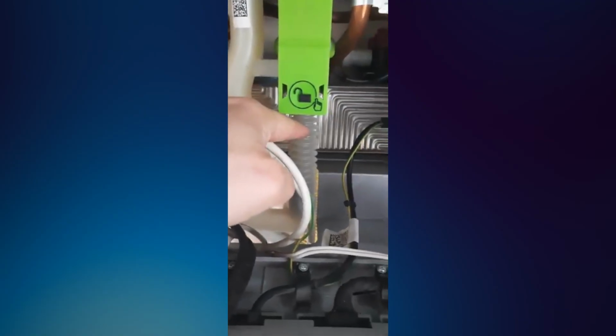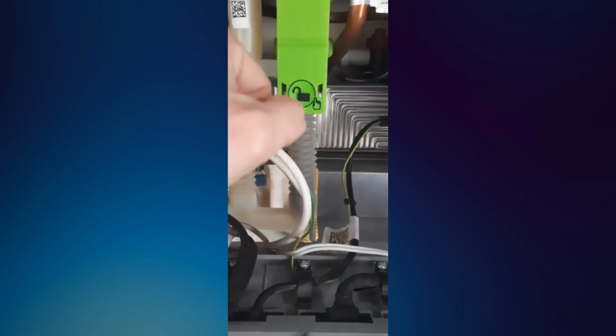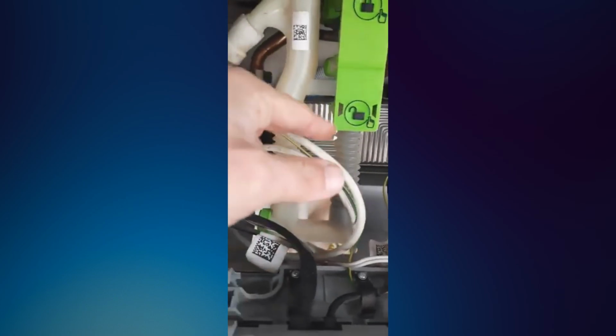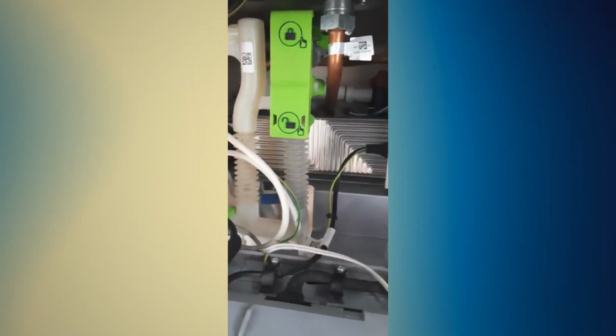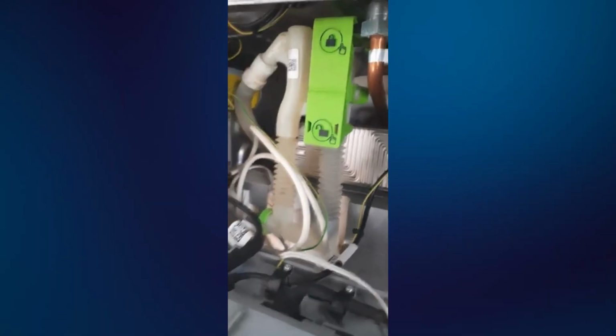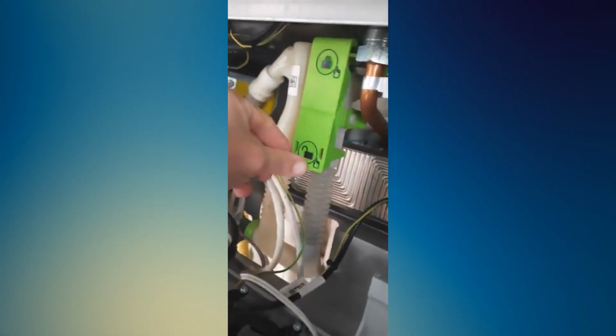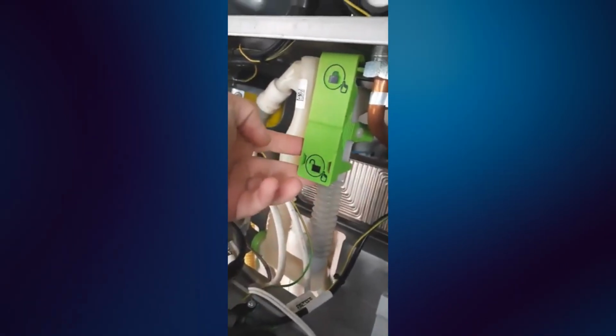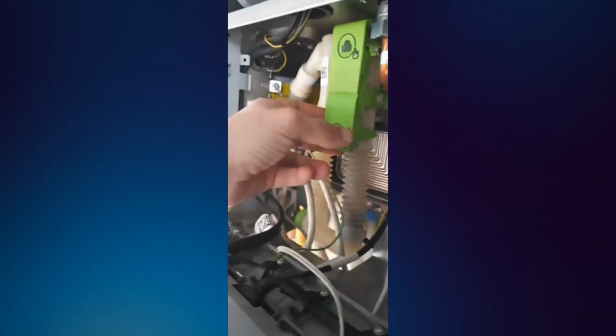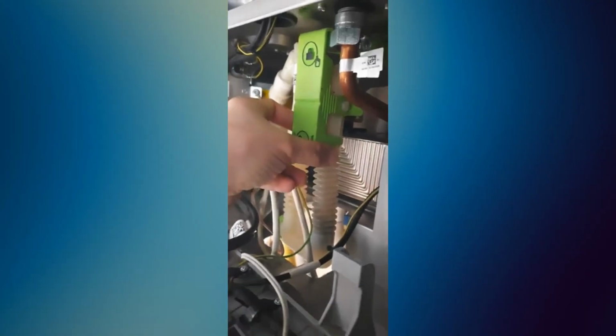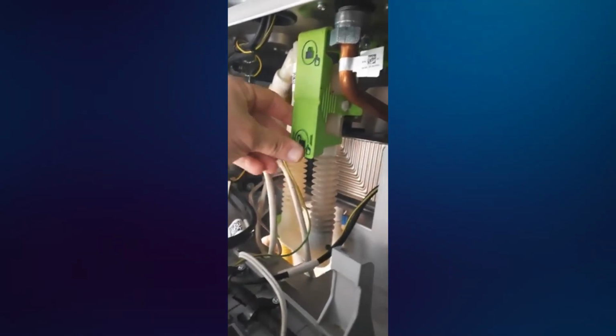The fifth possible cause is low gas pressure or gas flow problems. Even if gas is present, the pressure may drop when the boiler tries to fire. That can cause unstable ignition or flame loss. Possible reasons include a supply issue, undersized pipe work, a partly closed valve, a faulty regulator, or a gas valve problem inside the boiler. Gas pressure must be tested with proper equipment. It is not something to guess from the display.